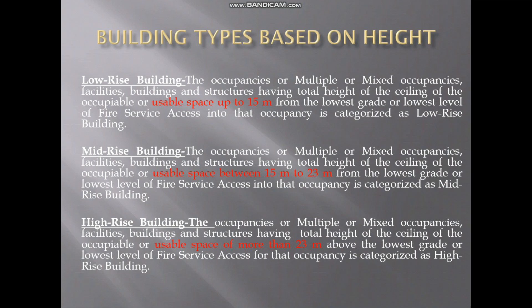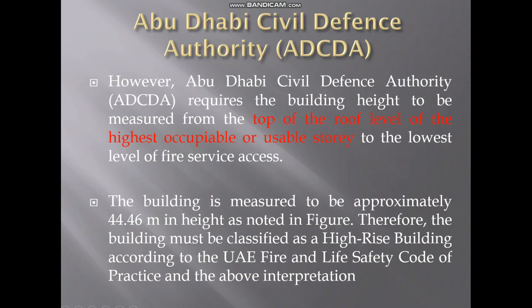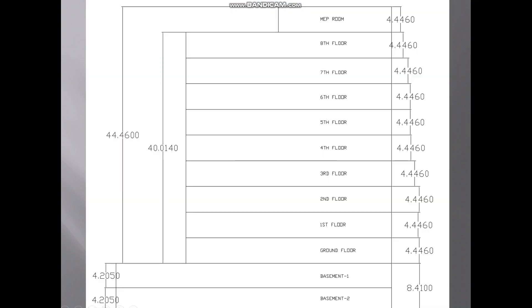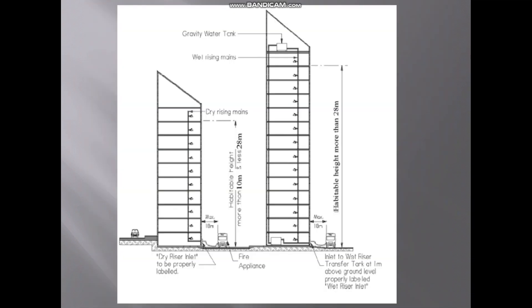Buildings with usable space up to 15 meters are considered as a low-rise building. From 15 to 23 meters is mid-rise, and more than 23 meters is a high-rise building. In our case, it is more than 23 meters, so this building is considered as a high-rise building.